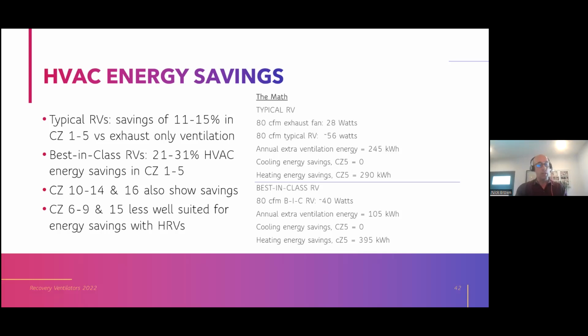The best in class ones boosted that to 21 to 31%. These are units with better than 0.7 watts per CFM and 85-90% recovery effectiveness. So there really is a case for looking at these high performance models. They make a big difference. In other climate zones, we found 10 to 14 and 16 showed lower savings than 1 to 5, and 6 to 9 and 15 were less well suited for energy savings with HRVs.